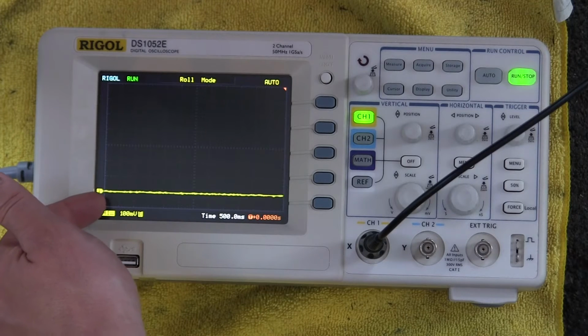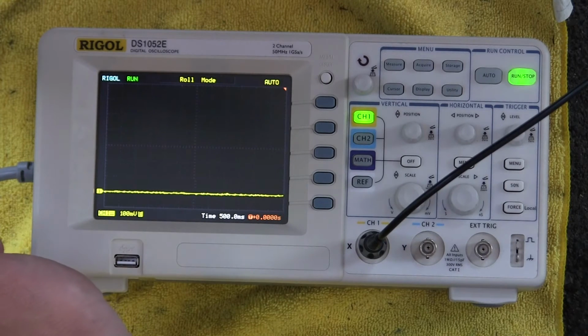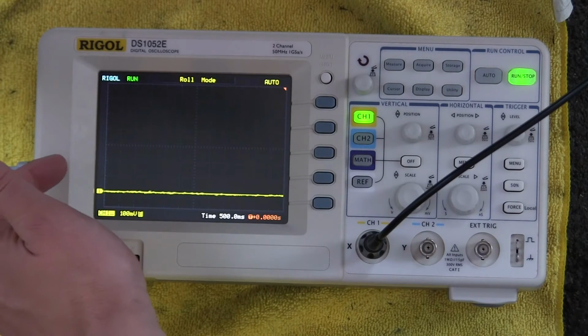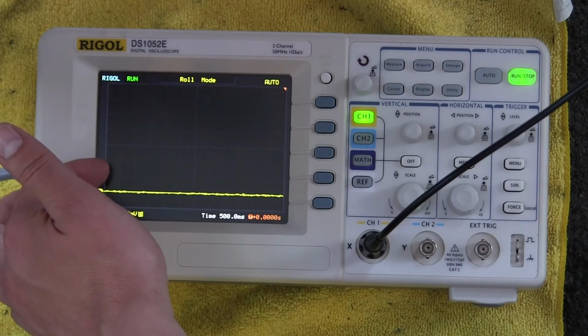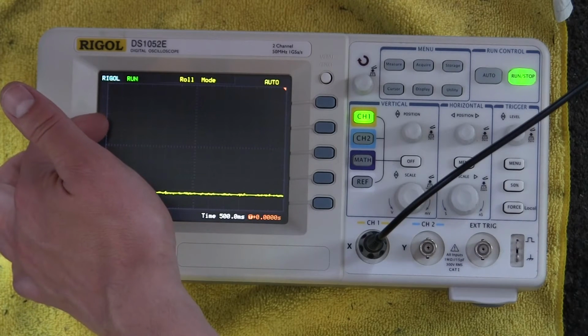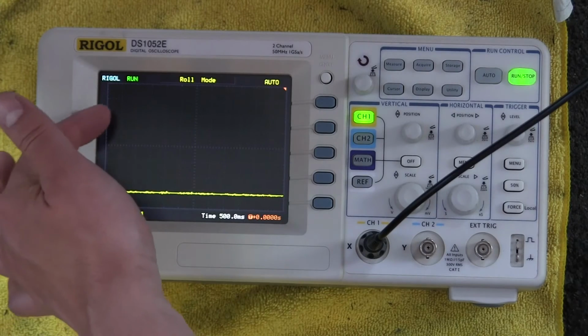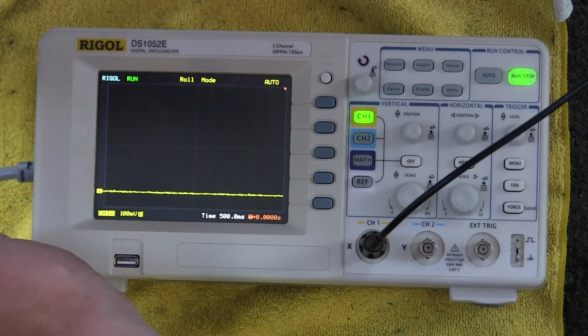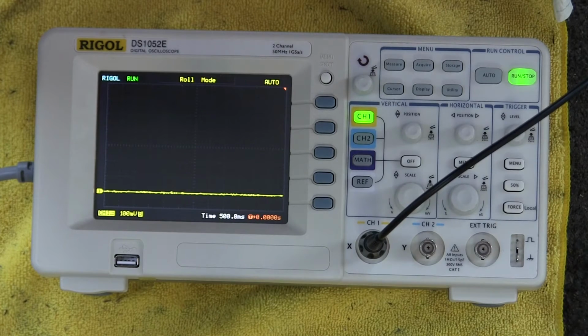So we expect this motorcycle to draw close to 400 amps when it cranks. 400 amps, so if 10 amps correspond to 12 millivolts, that's almost 1 millivolt per amp, so it should be a voltage drop of 0.4 to 0.5 volts, about half a volt. Here we have divisions 1, 2, 3, 4. Between here and here, this graph will jump when we crank the engine. Well, let's see how it goes. And this is with the small battery in there.